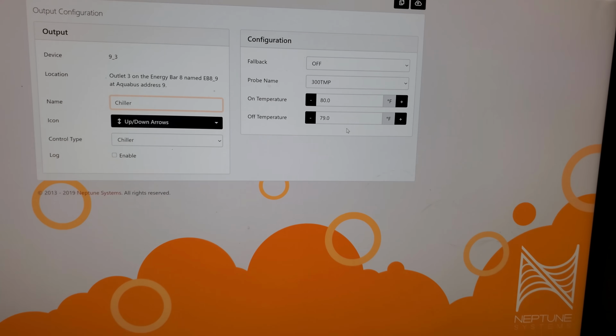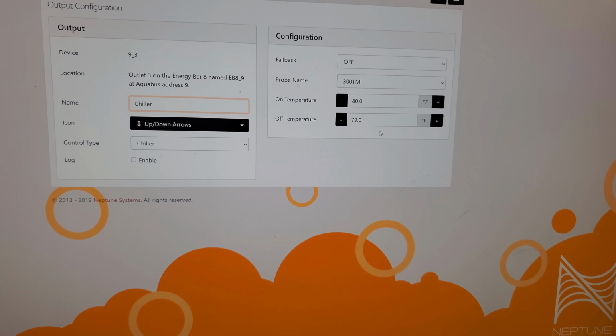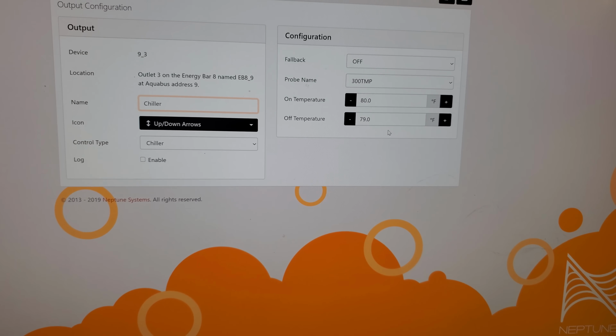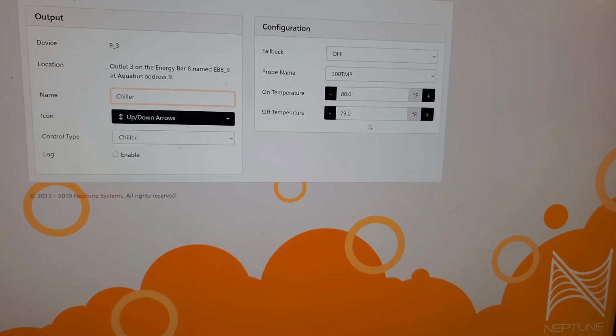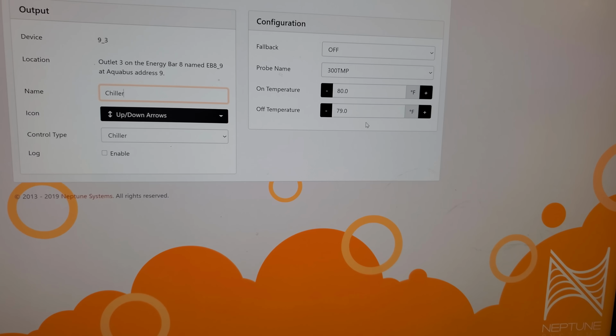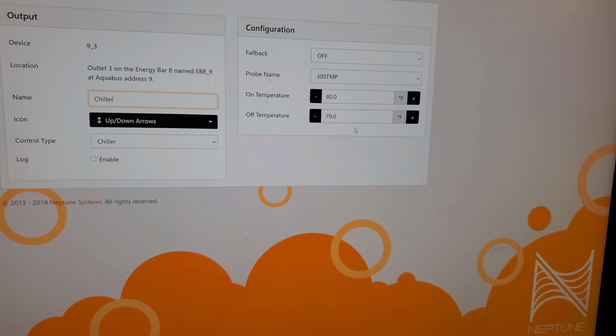So it's cooling it, and then it goes into all the tanks, and then it takes time for that water to get over to the probe to affect the temperature. Now, I want to see if it turns off at 79, what does the temperature actually end up at once it turns off? So we'll see.